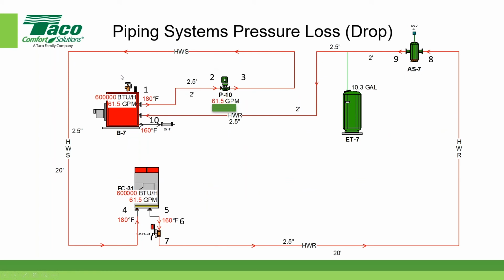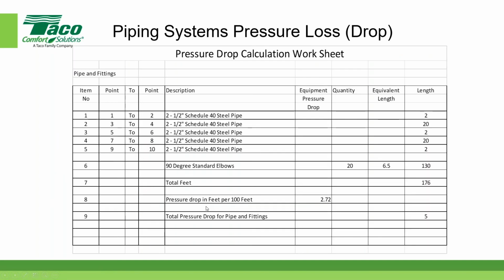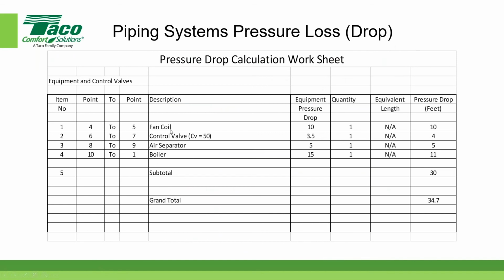So the very first piece of equipment would be the fan coil, and that's from point 4 to point 5 on my diagram. So from point 4 to point 5, there's my fan coil, and the only place you can get the pressure drop for this piece of equipment is from the equipment manufacturer. You cannot calculate that. You have to look it up. Whatever fan coil you chose for your system, you'd look at the manufacturer's data. And for that flow, in our case, it's a little over 60 gallons per minute. They publish the pressure drop, and in this case, it's 10 feet. The quantity in this case is 1. Equivalent length does not apply, and so the pressure drop is just 10 feet.